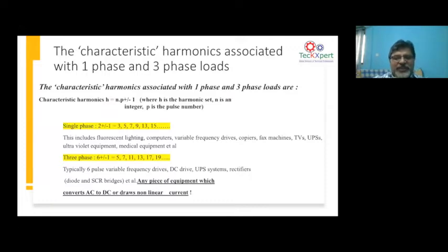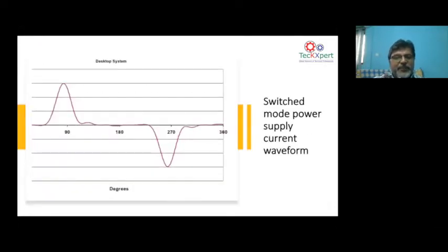Now go to the 3-phase, and as I told you, it has 6 diodes. So when you have 6 diodes, you go back to the same equation for harmonics produced by a 6 diode configuration: put N as 1, P as 6, you get 6 plus minus 1. That means 5th harmonic or 7th harmonic. Now we can see how a 3-phase device creates harmonics. It creates 5, 7, 11, 13 based on the same H equals NP plus minus 1 equation. So this is how the characteristic harmonics created by a single phase load or a 3-phase load are computed. Go to the next one.